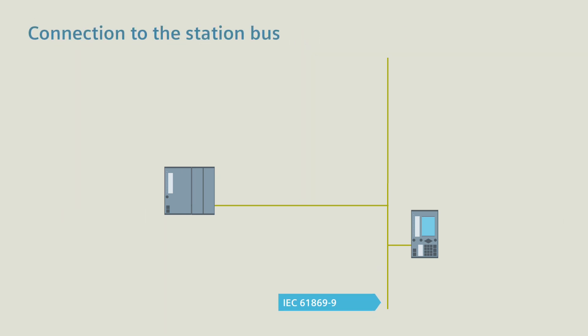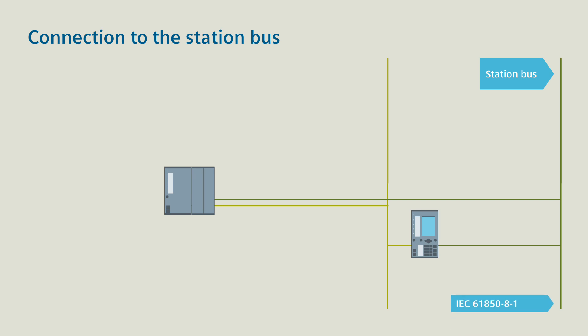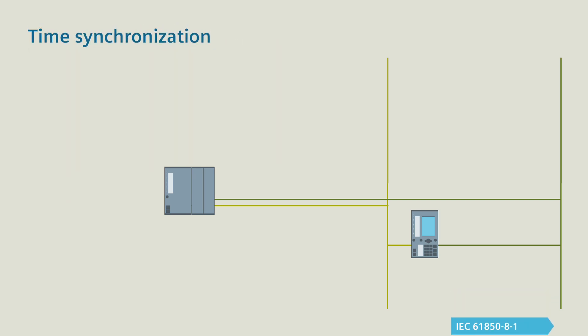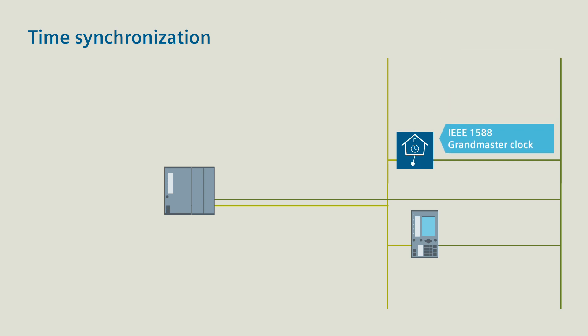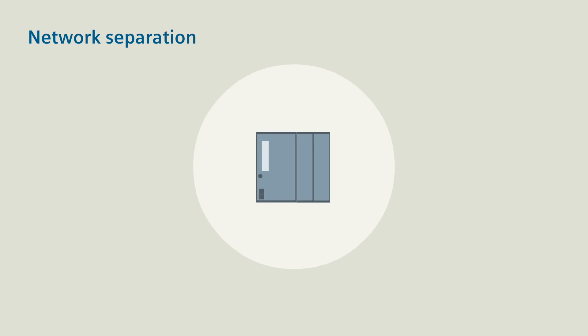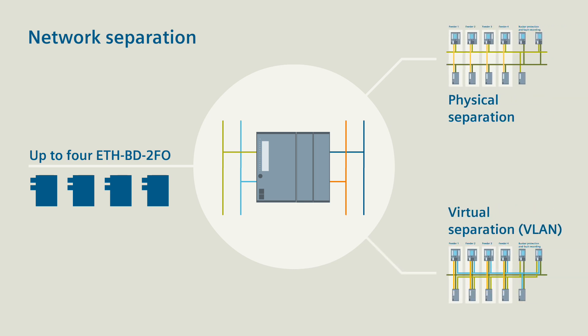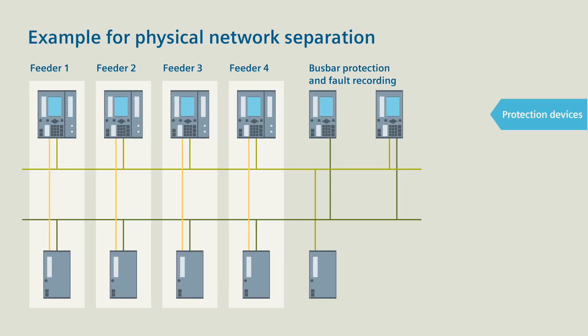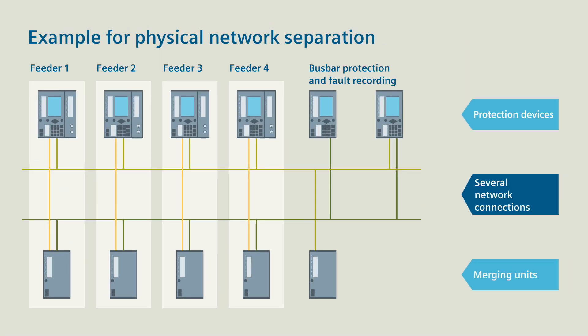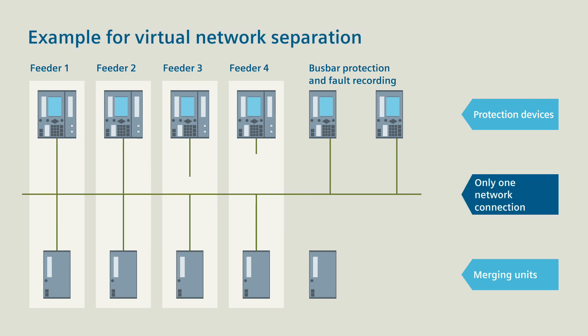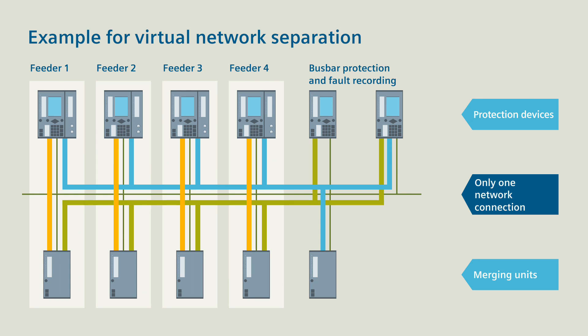With a further communication module, you can additionally connect the merging unit to the substation automation system. The time synchronization of the entire system occurs with an IEEE 1588 grand master clock. You can install up to four ETH-BD-2FO communication modules in one SIPROTEC 6MU85 merging unit. This enables up to four independent networks and allows you to separate these networks physically and virtually to diversify the network load. A network separation with several physical connections reduces the network engineering, while a network with only one physical connection and a virtual separation via VLAN reduces the network costs.